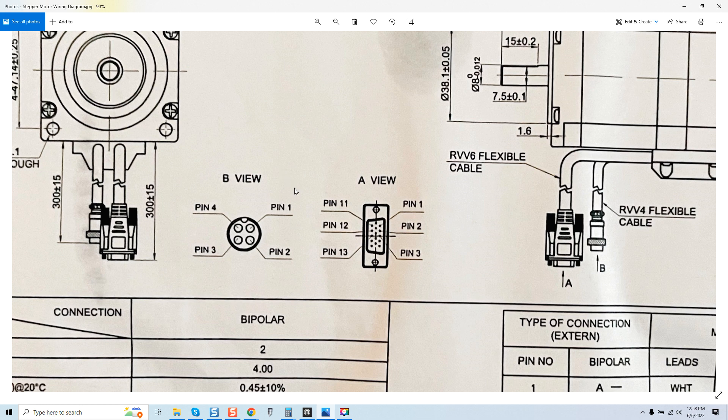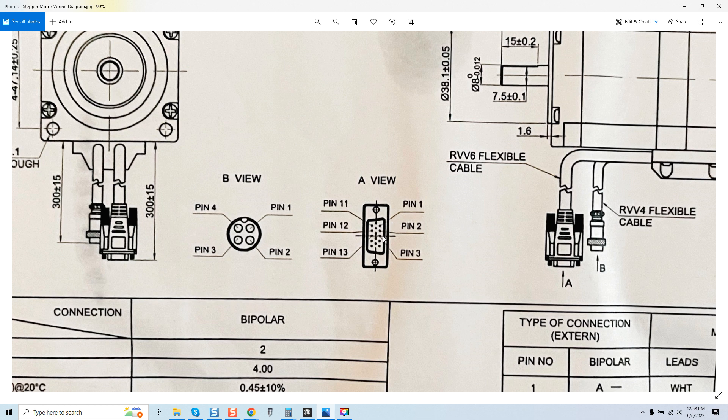So when we look at that we already know here we've got a connector that isn't shielded at all. DB9 connectors once again should be double shielded in terms of the cables being used. So again we need to extend those cables and we need to use double shielding. Now the question comes like it did with this client is what do I do about a connector here?